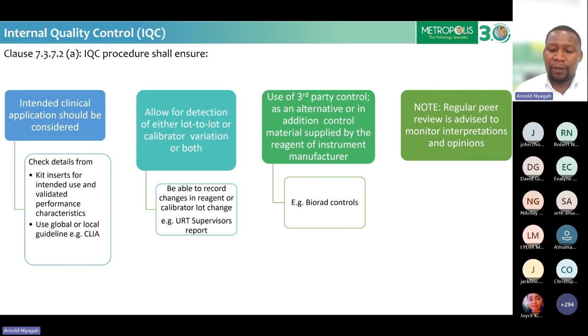In this case, if you're having a test like urea, that test has the intended use from the manufacturer. Once you check the kit insert for these tests, you will be able to see the intended use. You will also be able to see the performance characteristics and the analytical measurement range. Now you should be able to use these key T-certs and the performance characteristics to determine your IQC procedure. You can also use global and local guidelines, CLIA, EFLM, RICOS et al., to determine the allowable errors, and we'll be looking deeper into that as we go.